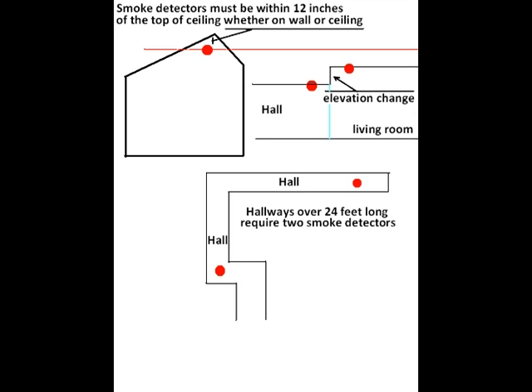You look at the second diagram to the right and you see hall, an elevation change. When you have an elevation change of 12 inches or more, you have to have another smoke detector. In this case, the smoke detector is in the living room, which it wouldn't matter if there was an elevation change or not. You would still have to have a smoke detector.